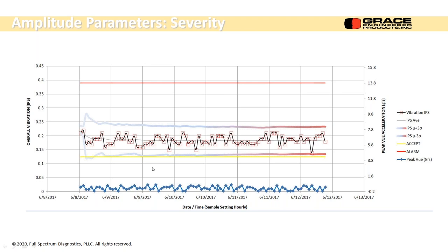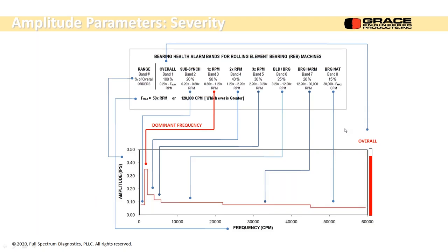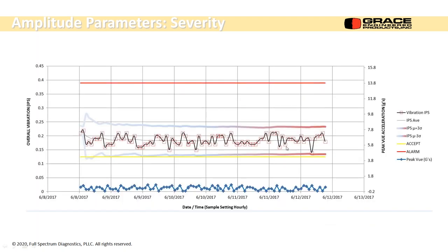You know, usually low vibration is good, but maybe it's the machine turned off. It shut down for some reason, and now I'm not taking any data, it's flat. And sometimes that happens. You'll run a machine, or you'll have a non-operating machine, and you won't know it until something else tells you. Okay. Oh, the other thing, we can trend more than one parameter.